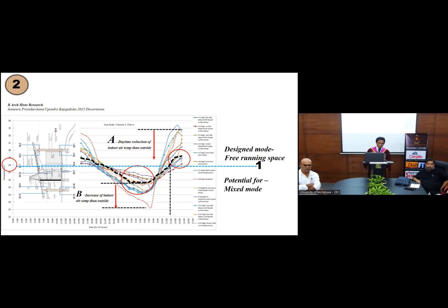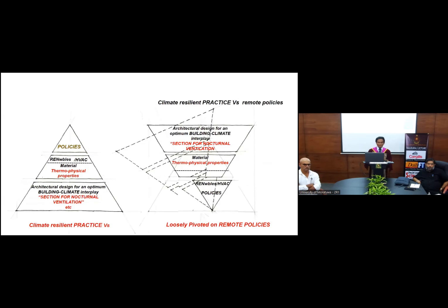So until 12 o'clock in the midday, during the daytime, this building works very well. But after 12 o'clock, its temperature increases. So it gives a good lesson for us because it's an opportunity to have mixed mode buildings in Sri Lanka. So you don't need to air condition the buildings from morning, right? If you design properly, you can have free running modes in the morning, but you can have air conditioners in the afternoon. So mixed mode buildings are the basis for that.